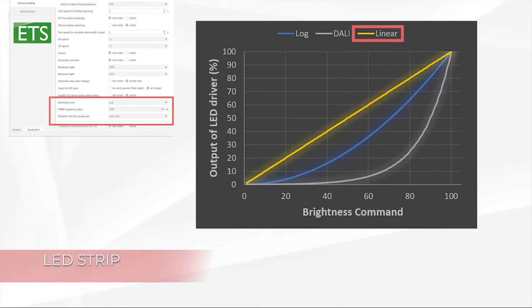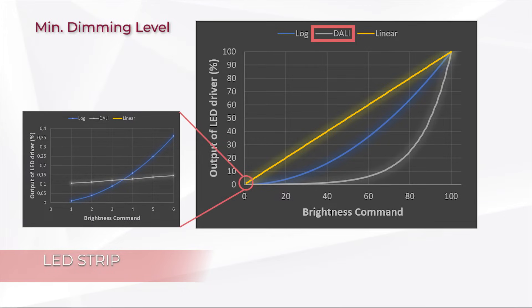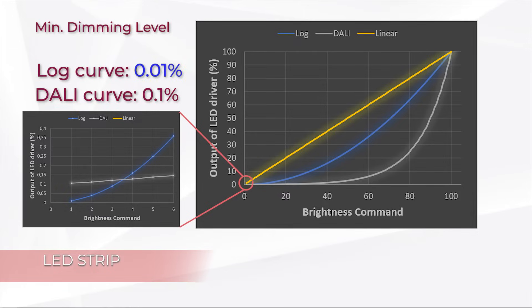The linear curve gives the driver output the same as the command sent from the push button. The DALI curve is based on a formula specified in the DALI standard, which gives the user an outstanding dimming experience, because the light difference between steps is designed to be constant and the minimal dimming level is 0.1% according to the standard. The LOG curve gives a logarithmic response, with a minimal output of only 0.01%, which opens the possibility for applications where low luminescence is needed. The user is free to select one of these three curves to achieve the best result.